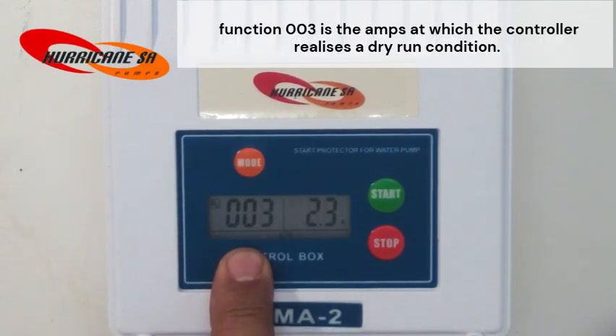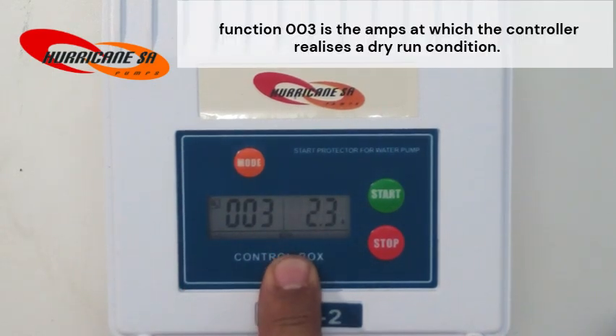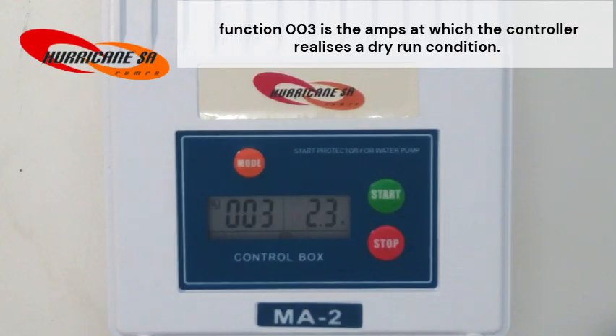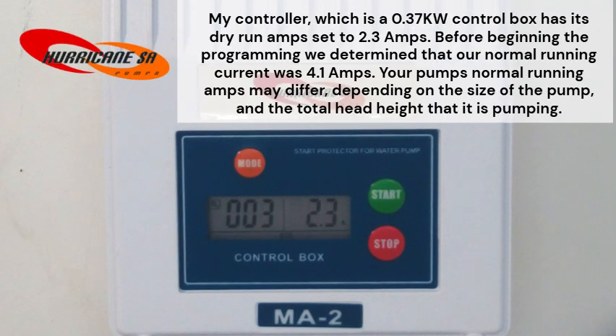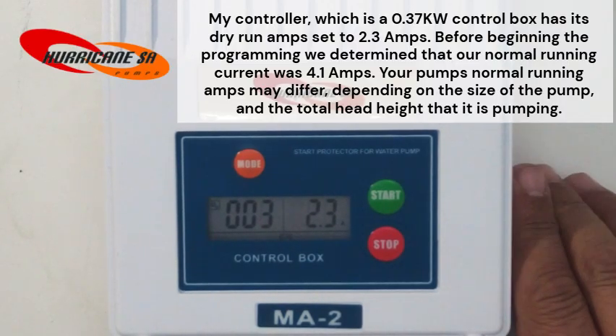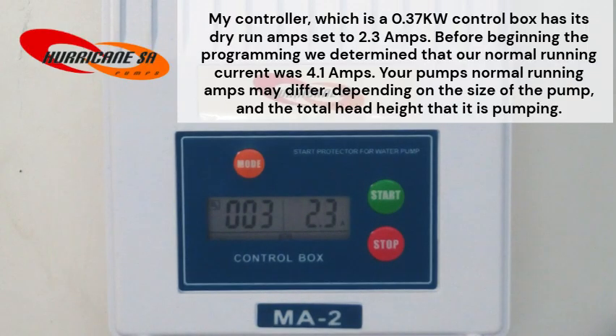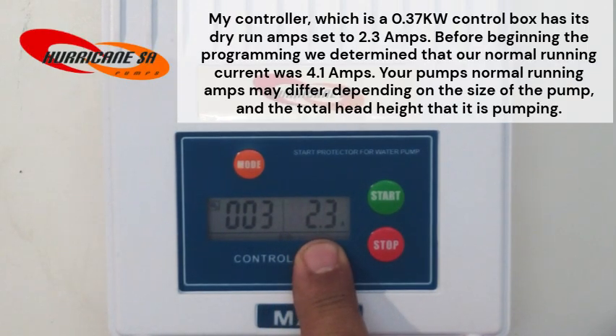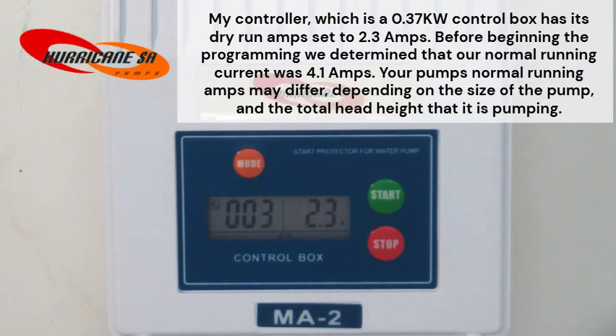Function 003 is a current at which the controller realizes a dry run condition. My controller, which is a 0.37 kW control box, has its dry run amp set to 2.3 amps. Before beginning the programming, we determined that our normal running current was 4.1 amps. Your pump's normal running amps may differ, depending on the size of the pump and the total head height that it is pumping.